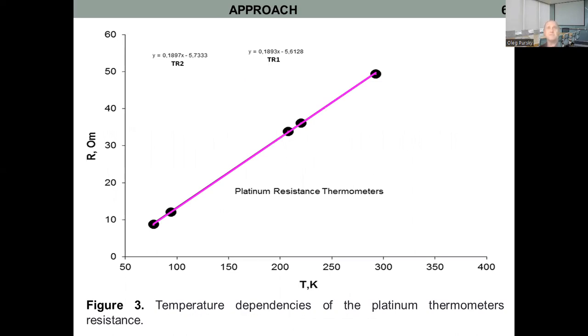The developed laboratory equipment has certain features and advantages compared to the prototype. Firstly, it is a wide range of temperature for measuring thermal conductivity. And secondly, it is compactness and economy in the use of the investigated substance and coolant, liquid nitrogen. The main feature of the developed equipment is the cooling mechanism of the cryostat by immersing its lower part in the transport reservoir with liquid nitrogen.